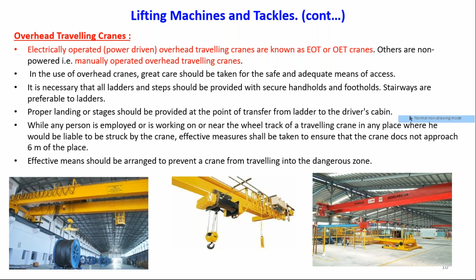While any person is employed or working near the wheel track of a traveling crane, in any place where he would be liable to be struck by the crane, effective measures should be taken to ensure that the crane does not approach within 6 meters of that place. This is an important criteria: there should be no movement or activity within the 6 meter zone of these cranes. Effective means should be arranged to prevent a crane from traveling into this dangerous zone.